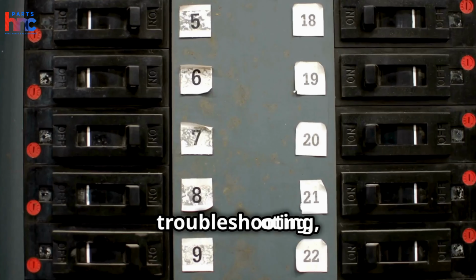First, check the fuse box or circuit breaker for tripped breakers or blown fuses. Open the access panel on your AC unit to locate the transformer. Inspect the wires for damage or burns, and replace any damaged wires. Use a multimeter to test the voltage going in and out of the transformer.